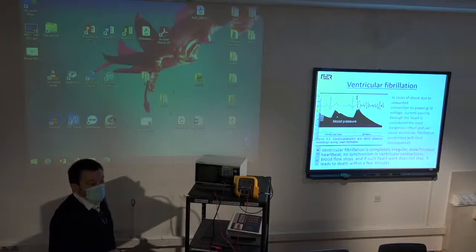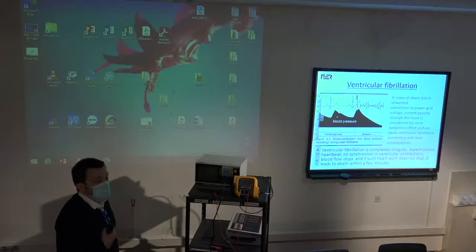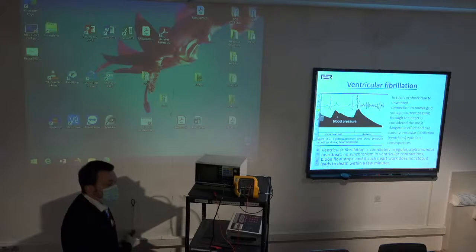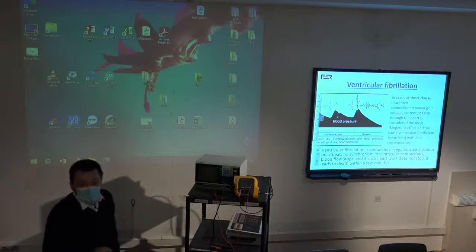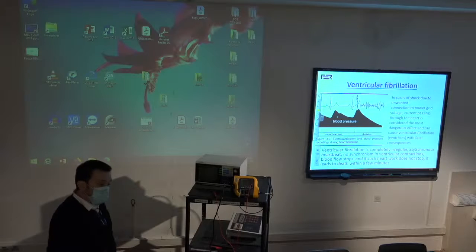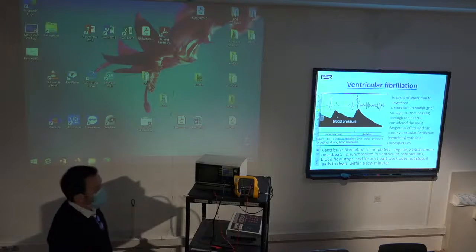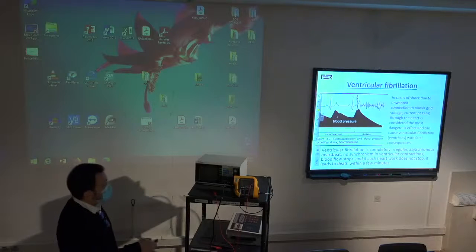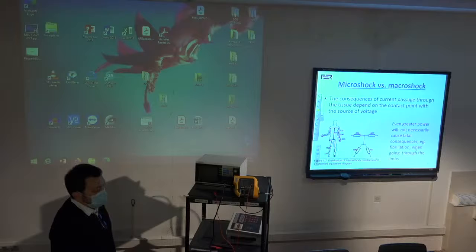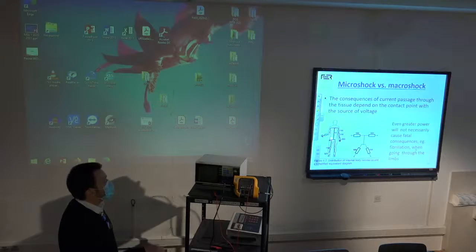So whenever some current is introduced close to the human heart, it should be synchronized with the ECG, so that the first edge of such a pulse does not come at the time of that part of the T wave. For the analysis of different currents to different parts of the body, different segments have been developed as a model of the human body.